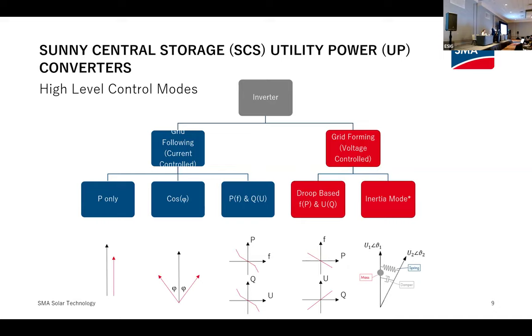A quick graphic of the different control modes: grid following on the left, where we dispatch active and reactive power in different fashions — you can prioritize active power over reactive power, or vice versa, program the inverter to operate at a specific cosine phi or a specific power factor, or follow predefined curves. In a grid forming inverter, we use droop-based controls where power is a function of frequency, or reactive power is a function of voltage. And then we also have layered on top of this what we call an inertial mode.